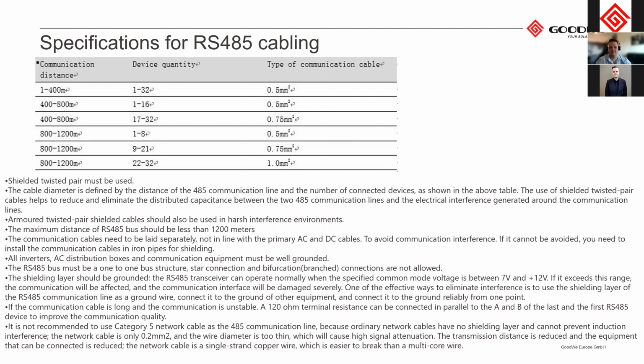0.5 millimeter is fine. It's only when you have more than 17 inverters and you're exceeding that 800 meters that we have to increase that cable thickness to 0.75. So normally at 0.75, I think you do get some Cat6 that do have larger conductors. Otherwise, one would have to use specific RS485 shielded cabling.